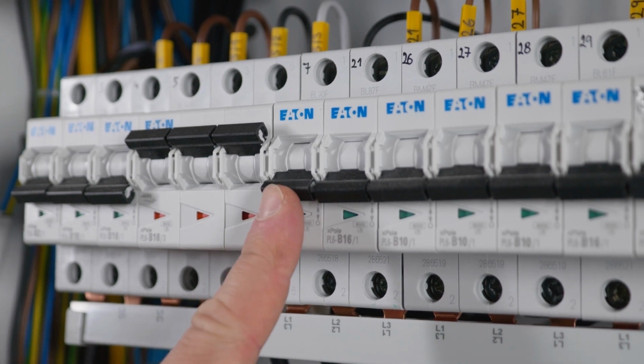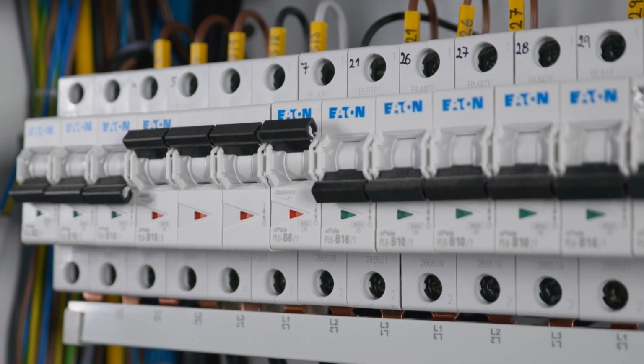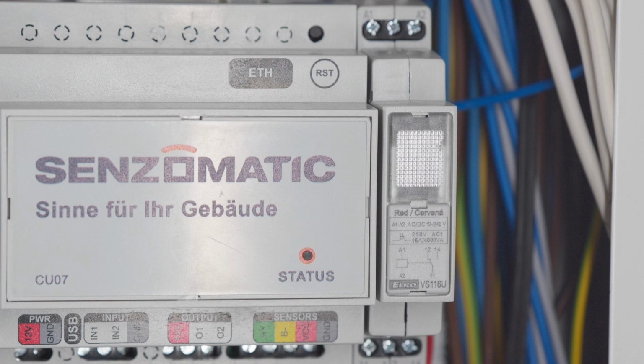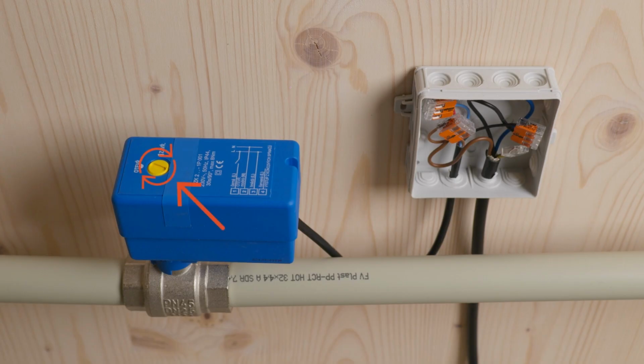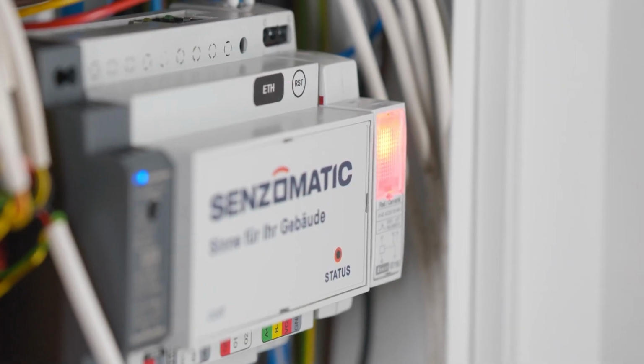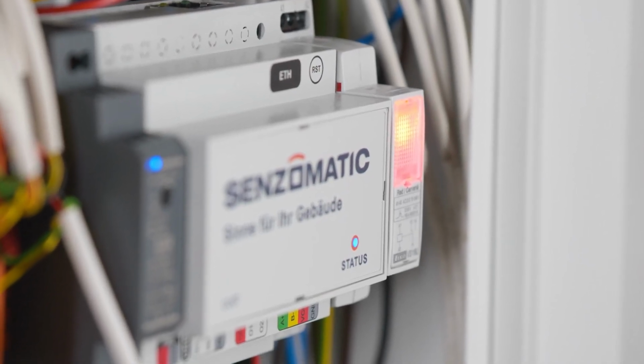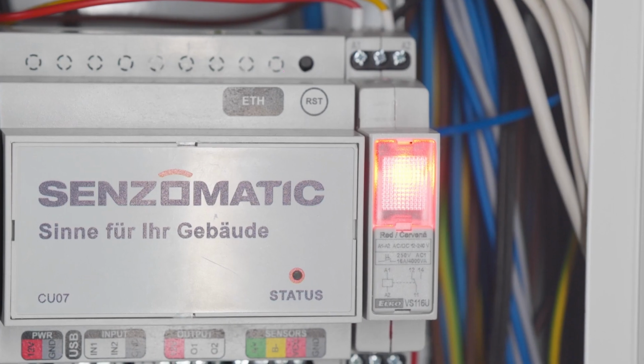Turn the circuit breaker on for both the central unit and the valve. The relay should be open and should not be lit up. If the relay is not lit up, the valve must be open. If the valve starts to close after it's switched on, change the wiring of the control wire according to the attached diagram. If the relay lights up immediately after the central unit is switched on, please check the relay control wires.